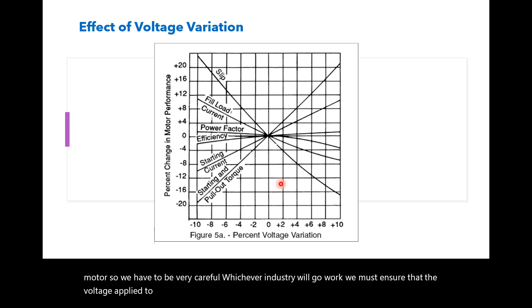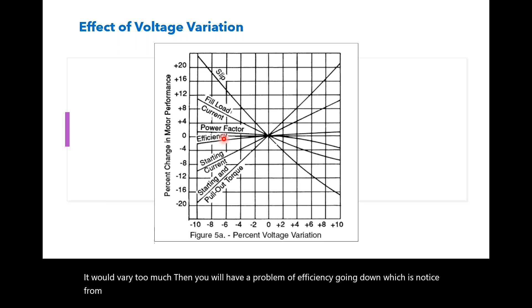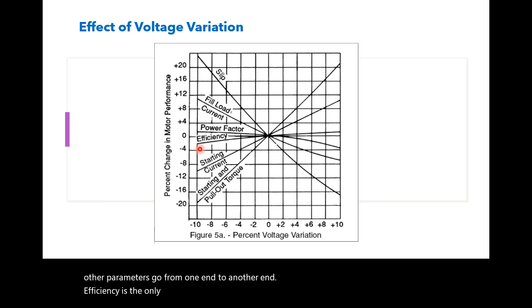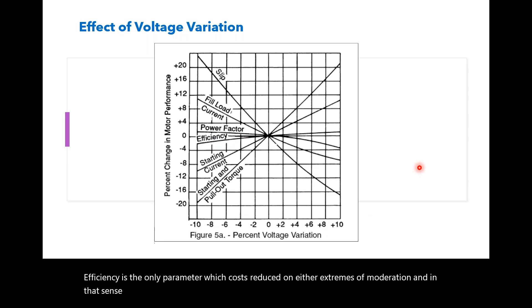So in this sense, voltage variation is an undesirable component for operating a motor. We have to be very careful. Whichever industry we go work in, we must ensure that the voltage applied to the motor terminal does not vary too much in the course of a day. If it varies too much, then efficiency goes down, which you notice from this curve. The efficiency goes down on both extremes. This is a unique feature. While all other parameters go from one end to another end, efficiency is the only parameter which is reduced on either extreme of voltage variation. In that sense, voltage variation is an undesirable element.